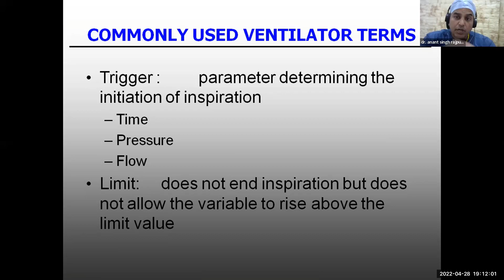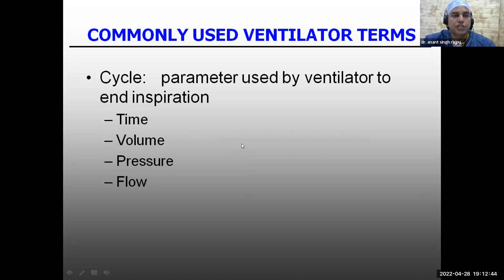So there can be time cycle. So I say that for 1 second, from this point to this point, a flow will be delivered, and after 1 second, the flow will stop. So after 1 second, or 0.8 second, if the flow is stopping, that means it's a time cycle mode or time cycle parameter. We can have volume as a cycle, that 500 ml of volume is to be given. Once the 500 ml is achieved, then the inspiration will stop. So you can have volume cycle. Similarly, pressure cycle, we can have flow cycling.